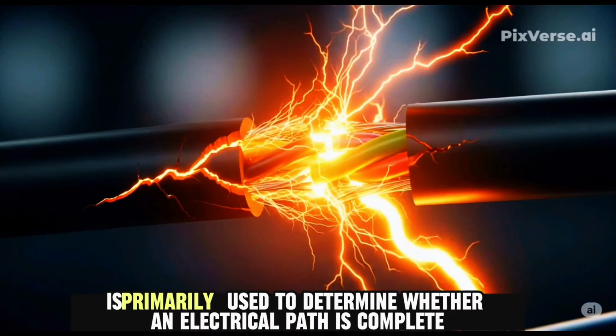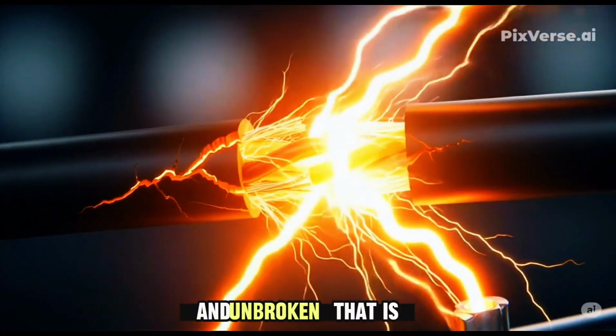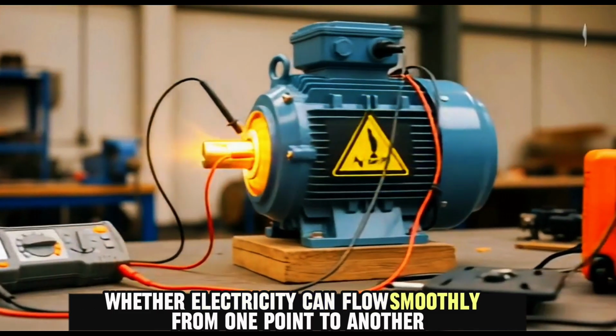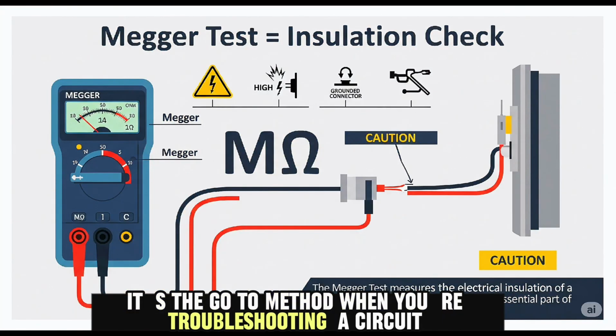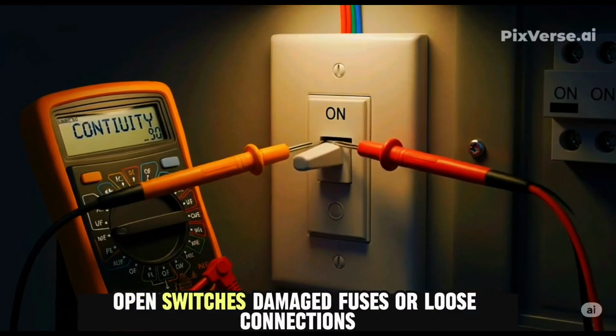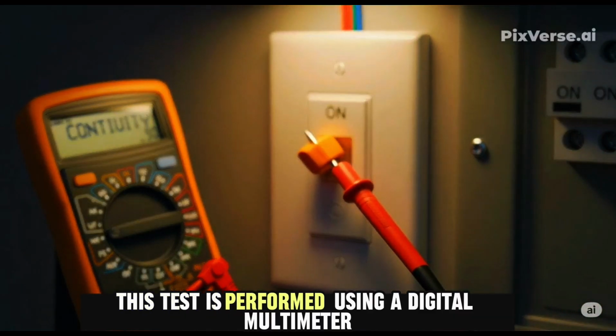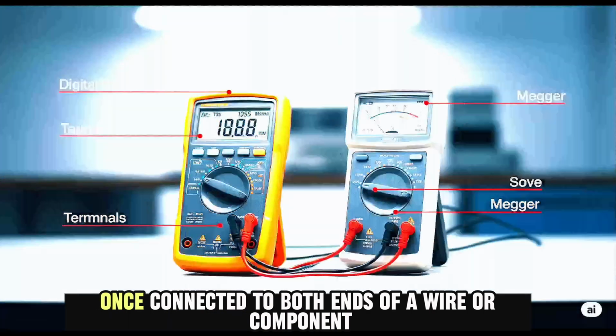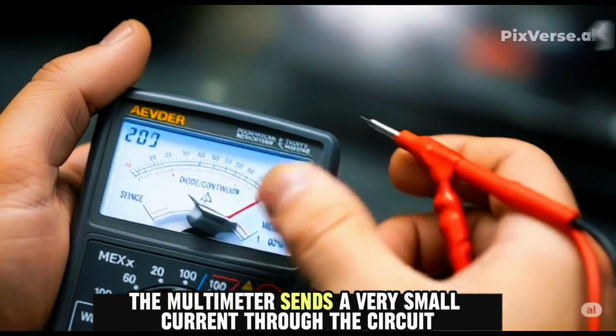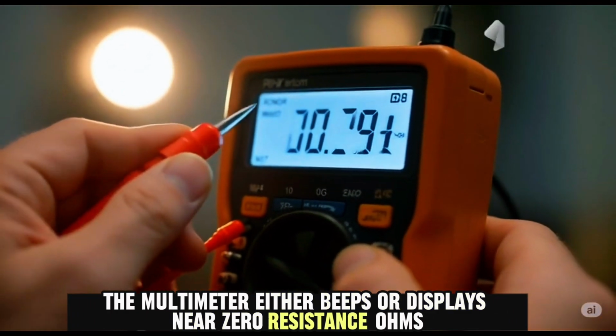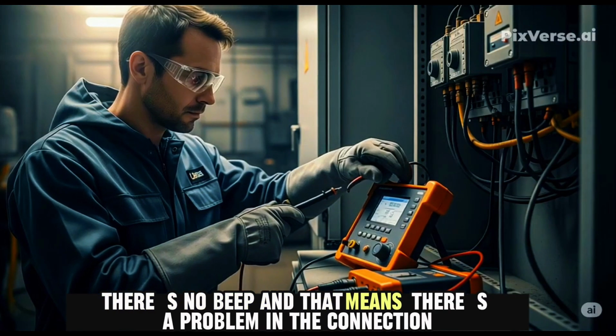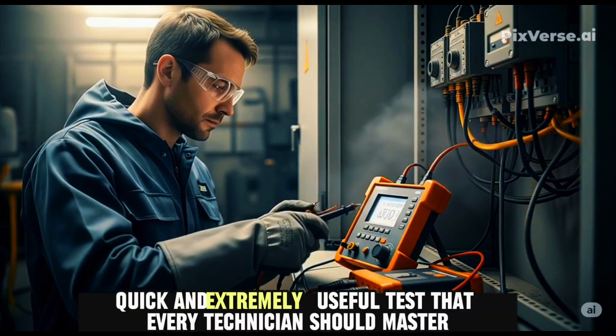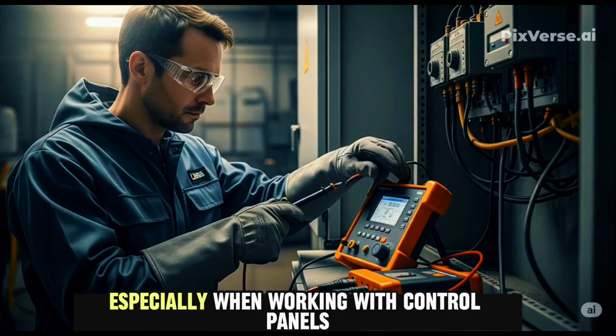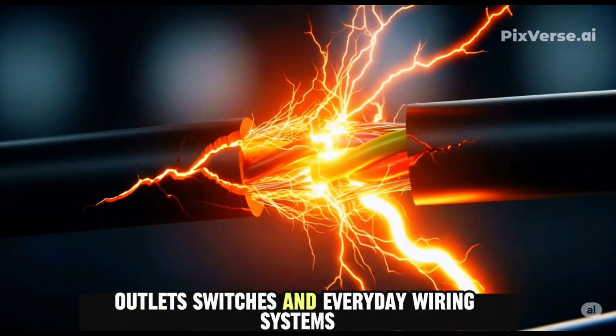A continuity test is primarily used to determine whether an electrical path is complete and unbroken. That is, whether electricity can flow smoothly from one point to another. It's the go-to method when you're troubleshooting a circuit, checking for broken wires, open switches, damaged fuses, or loose connections. This test is performed using a digital multimeter set to continuity mode. Once connected to both ends of a wire or component, the multimeter sends a very small current through the circuit. If the path is continuous, the multimeter either beeps or displays near zero resistance, ohms, usually somewhere around 0 to 1 ohm. If there's a break or high resistance, there's no beep, and that means there's a problem in the connection. It's a low voltage, quick, and extremely useful test that every technician should master, especially when working with control panels, outlets, switches, and everyday wiring systems.